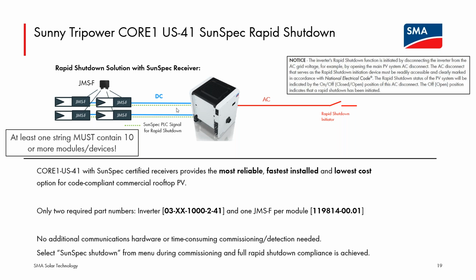So while there are 6 tracking channels, potentially 6 different string lengths coming to each CORE1, we're saying one of those strings needs to be at least 10 module-device pairs long to ensure that there's enough DC voltage on at least one of the inputs to boot the system back up. So at least one string or channel coming into the CORE1 needs to be 10 modules long. The other ones could be shorter. Generally, that's not much of a concern on our commercial systems, but I wanted to include that. It's slightly different than the published SunSpec standard.